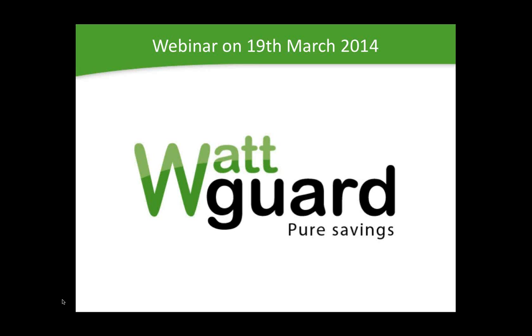What would be the consequence when there is voltage fluctuation? Yeah, that's a very good question. In the first version of our cabinet, we would all the time make sure that the system would be running to comply with the lowest level of voltage that we would detect or measure during a period, to make sure that it would cope with such a drop in voltage. What it meant actually was that the saving was not really optimized.